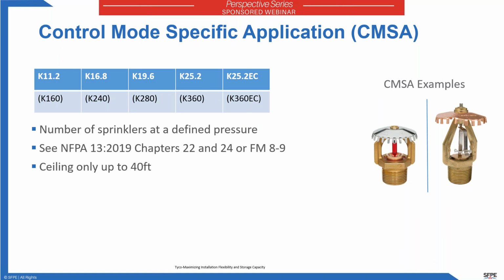Control mode specific application sprinklers, or CMSA, I believe started to come about in the early 70s. The first one may have been the large drop sprinkler. This sprinkler protection for storage applications is different. It's not based on area or density. The hydraulic designs are based on a number of sprinklers at a defined pressure. If you go to chapters 22 or 24 of NFPA 13 2019, you'll see protection schemes for CMSA sprinklers, and they focus on the number of sprinklers and pressure based on the commodity classification, storage arrangement, as well as the ceiling height and storage height the sprinkler is going to protect. So you might see a protection scheme that calls out 15 sprinklers at 25 psi, or 10 sprinklers at 40 psi. So we're not concerned about the area.